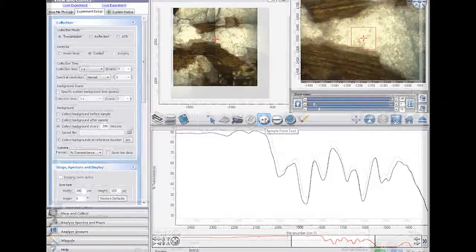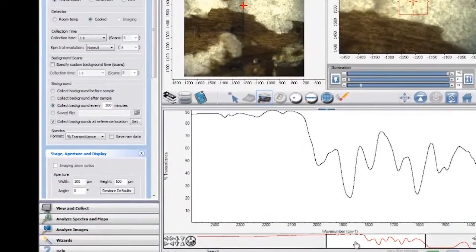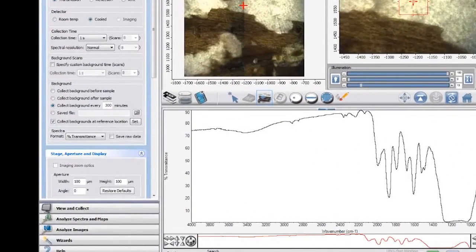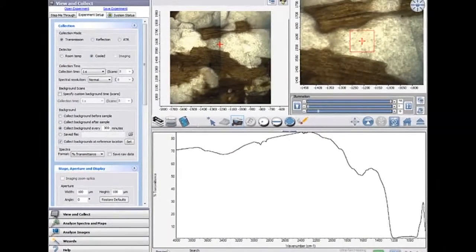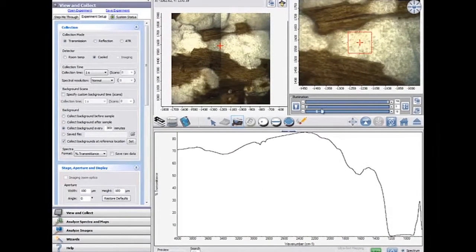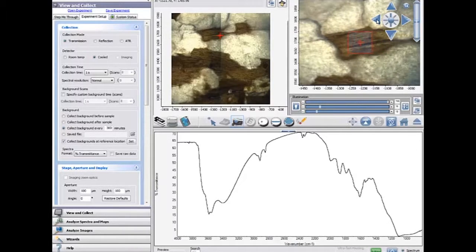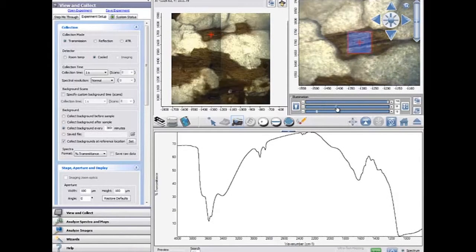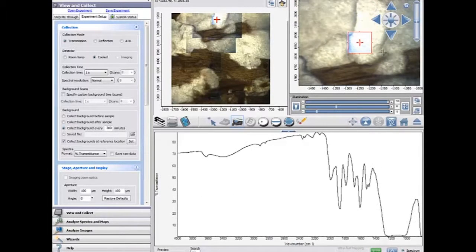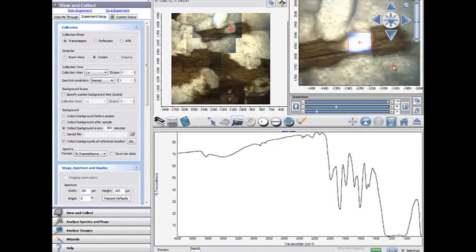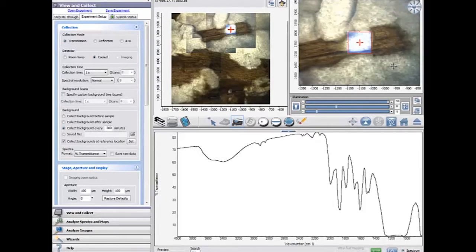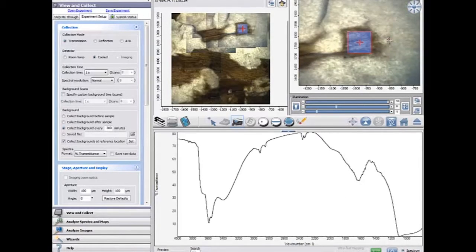Like all Thermo Scientific infrared microscopes, the Nicolet iN10 operates with true real-time view and collect, showing you live video and live infrared spectra continuously. You graphically select the specific point for analysis using the automated aperture system. The off-axis aperture never blocks your view of the specimen. A backlit illuminator physically confirms you have selected the correct region of interest. These active preview scans are a result of a single scan.